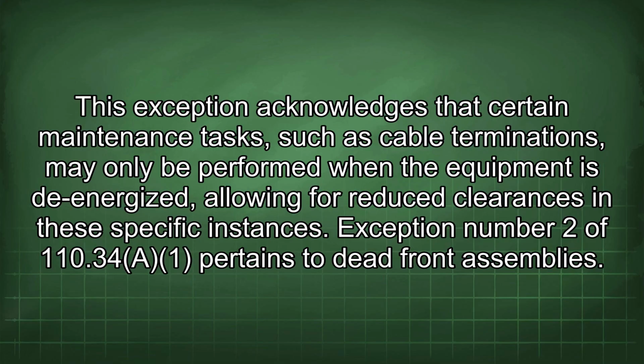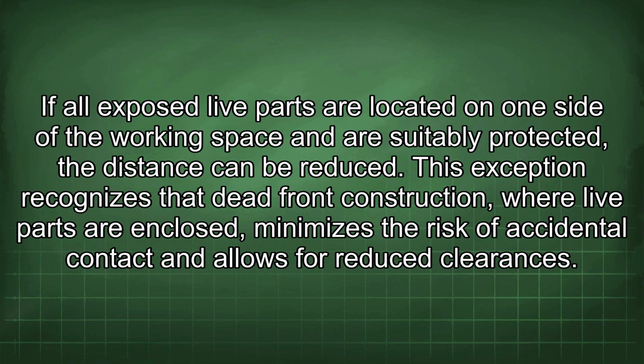Exception number 2 of 110.34(A)(1) pertains to dead front assemblies. If all exposed live parts are located on one side of the working space and are suitably protected, the distance can be reduced. This exception recognizes that dead front construction, where live parts are enclosed, minimizes the risk of accidental contact and allows for reduced clearances.